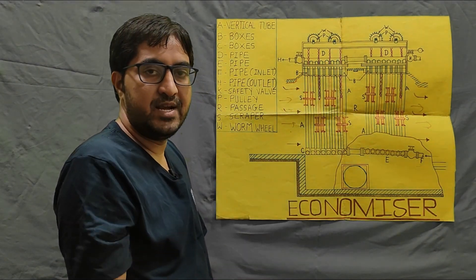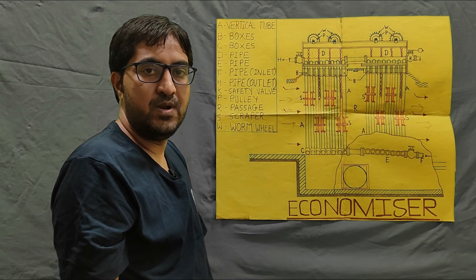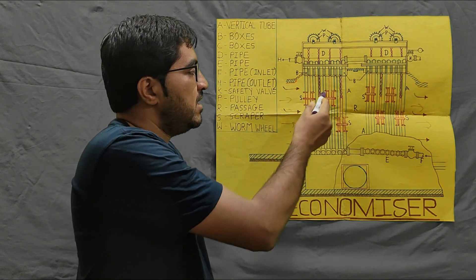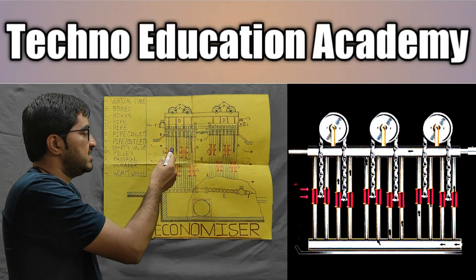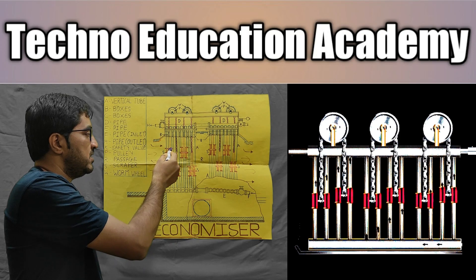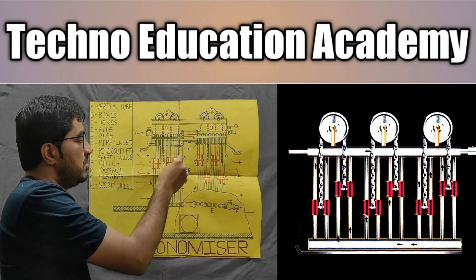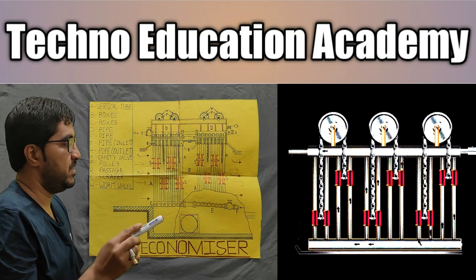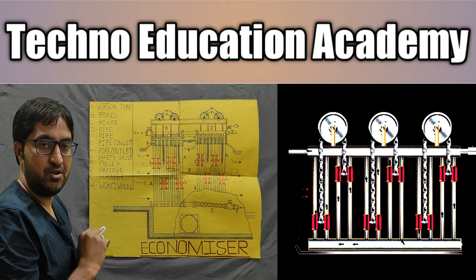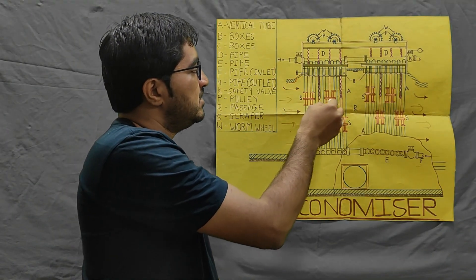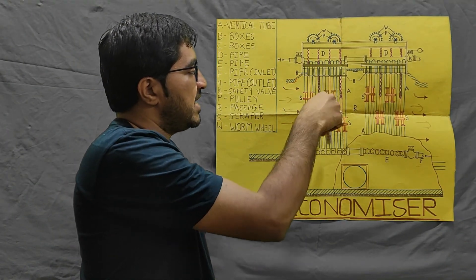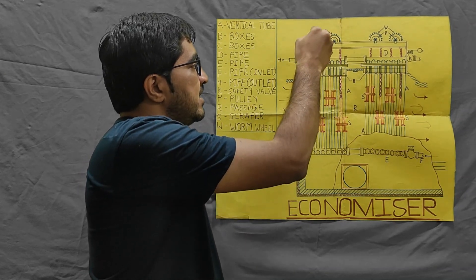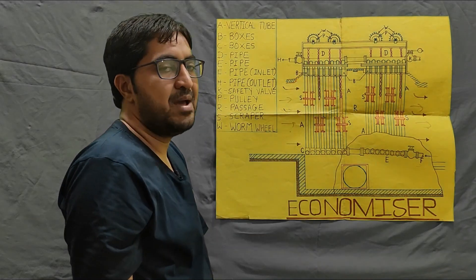Sometimes in the flue gases there are carbon particles, which precipitate on the surface of the tubes. Since carbon is an insulator, it reduces the heat transfer rate of the tubes. To address this, we use a scraper mechanism. The scraper slides up and down and removes the carbon particles from the tubes, so we can achieve the maximum heat transfer rate between the flue gases and the water tubes. The scraper is connected with a chain, and the chain is connected with the worm wheel, which is operated by a motor.